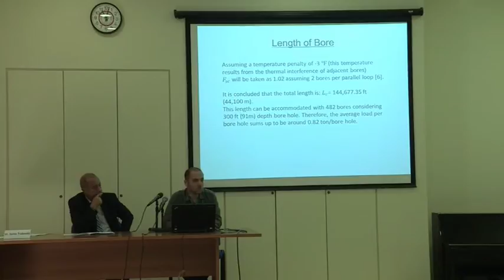We ended up by identifying the lengths needed to dissipate 1400 kilowatts within the ground, and it ended up to be 44 kilometers. Based on a depth of 100 meters of bore, we needed 482 bores to cool that, to just dissipate 1400 kilowatts. So we started identifying the cost versus the benefit. Another drawback is the low electricity rate in Qatar, which is 3 cents per kilowatt hour. So we ended identifying that even though we have a daily saving of 3100 kilowatt hours per day, the saving is reduced by the low electricity rate that's provided in that country.